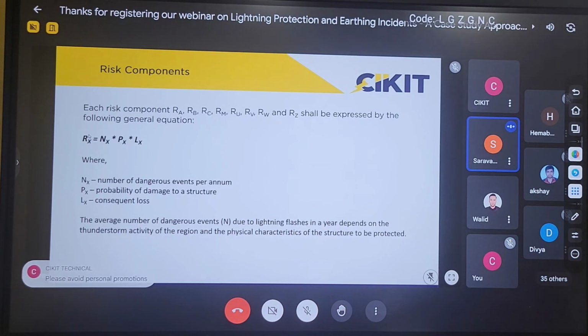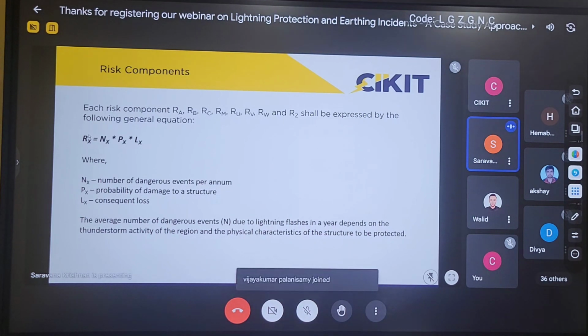So the three components written are the number of dangerous events per annum, the probability of damage, and the consequent losses. If I consider all these three parameters, the first one is the number of dangerous events per annum.